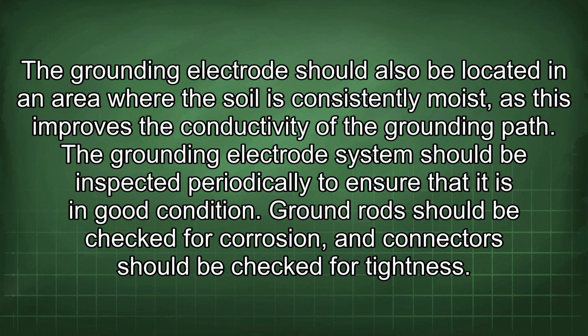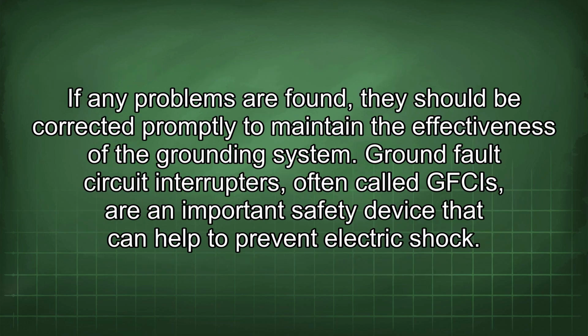The grounding electrode system should be inspected periodically to ensure that it is in good condition. Ground rods should be checked for corrosion, and connectors should be checked for tightness. If any problems are found, they should be corrected promptly to maintain the effectiveness of the grounding system.